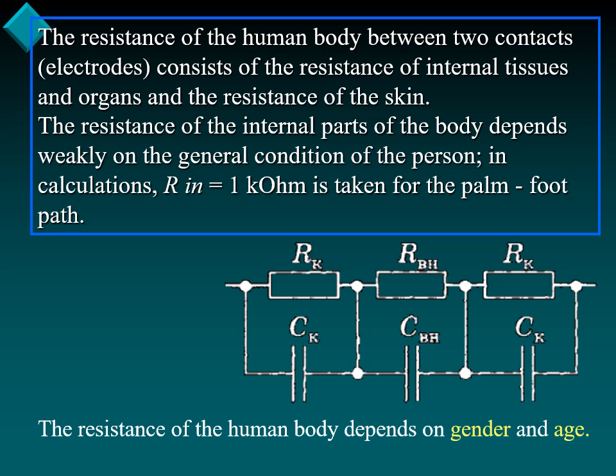So therefore, in most situations, the current flowing through the body mainly depends on the state of the body at the point of contact. Dry skin has a high resistance, and wet skin will, of course, have a low resistance, since the ions in the moisture will ensure the passage of body currents. With dry skin, the resistance between the extreme points of the body, that is, from palm to foot, can be equal to 10^5 ohms, and with wet skin, it can be 1% of this value. The total resistance of the body between sweaty hands is equal to about 1,500 ohms.